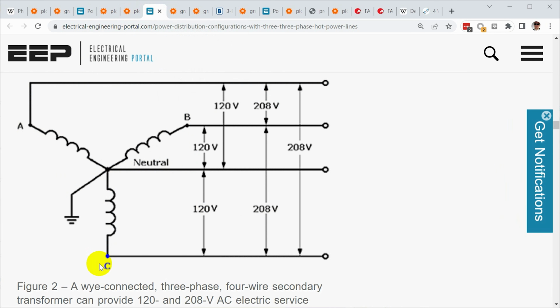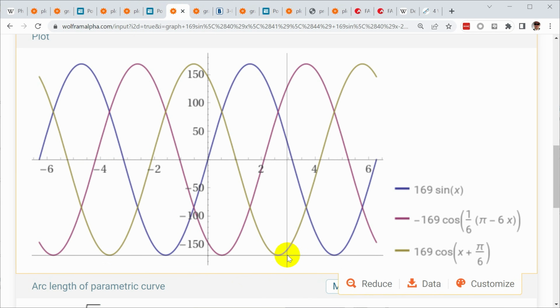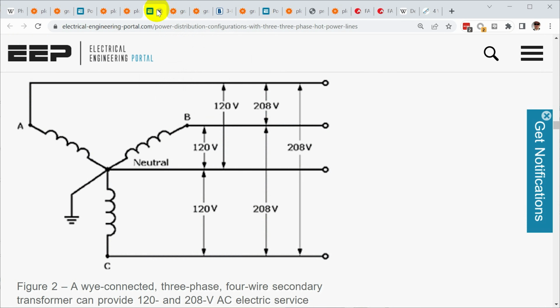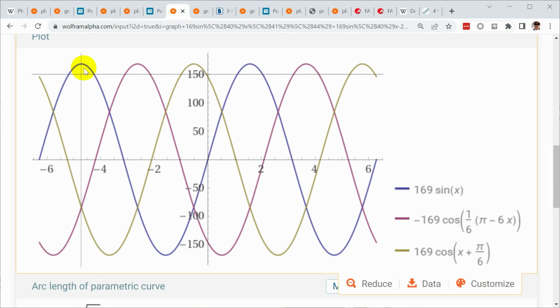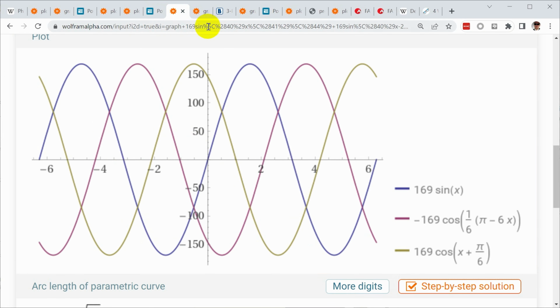And then each of these legs is 120 volts with respect to that neutral, but out of phase by 120 degrees. So the waveform looks like this. Now you can see this is peaking above 120 volts. It's actually up around 169 volts. And that's because that 120 volts is RMS. That's a root mean square measure of the voltage. The actual peak of the voltage is higher than that. So if you're looking at A or B or C with reference to the neutral, you're going to see 120 volts RMS on each one of those.